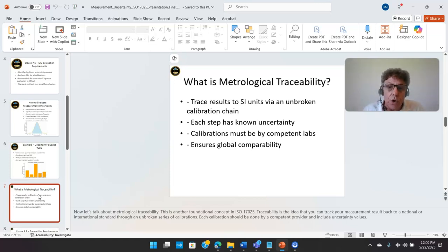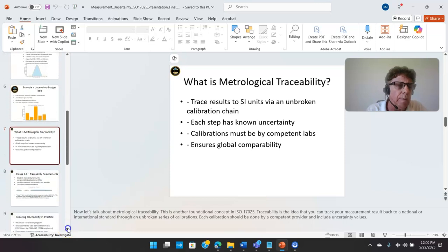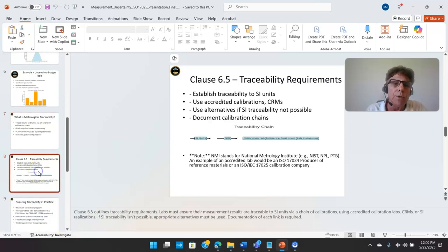So you want to make sure that you're communicating with these providers to specifically let them know you want your calibration performed in accordance with ISO 17025. It's very important that you make that delineation. So section 6.5, traceability requirements. We want to establish traceability to the SI units. Use, like I said, accredited calibration providers under 17025.